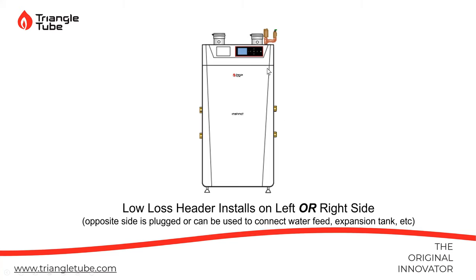If you want to go over to the left side here, you'll need an 18-inch nipple to get you right outside the jacket. You can go longer, but to get you outside with enough room to get your drip leg on, it's about 18 inches. And you can go either side. We went back and forth with a lot of contractors on what we wanted to see, but ultimately that gave us the most universal install. Just keep in mind, before you tuck this thing up against the wall, put that 90 and those nipples on. That way it's sticking out and you can easily install your gas line after you put it in there.